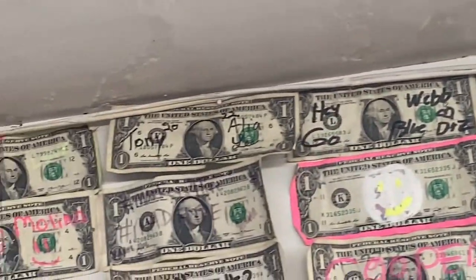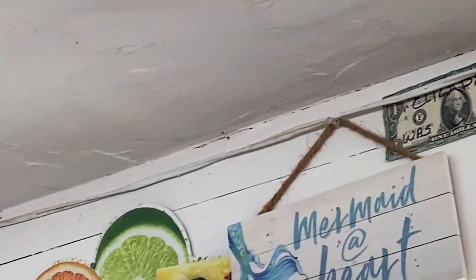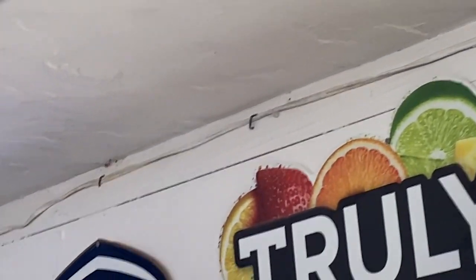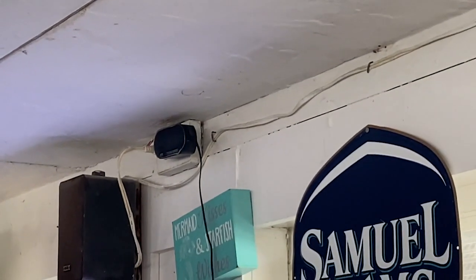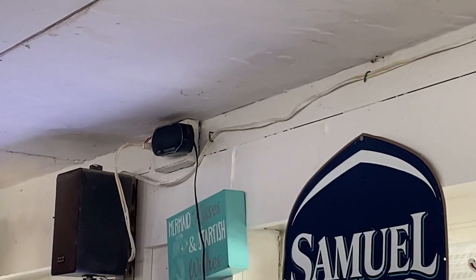Look how this exit sign is wired all the way down the wall. Using the power supply cord like this and securing it to the surface of the building — that's a violation of 400.12.